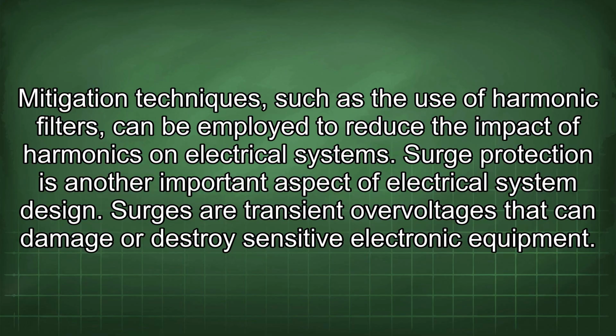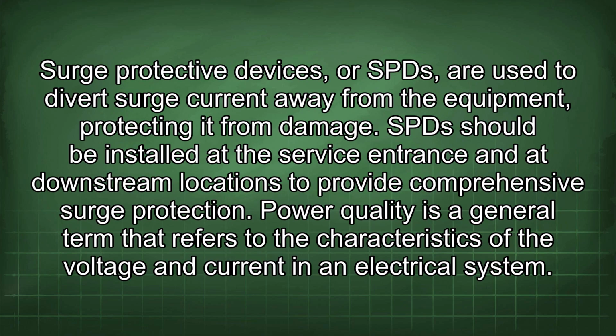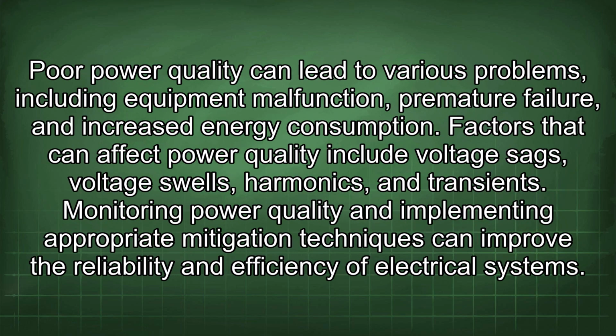Surge protection is another important aspect of electrical system design. Surges are transient overvoltages that can damage or destroy sensitive electronic equipment. Surge protective devices, or SPDs, are used to divert surge current away from the equipment, protecting it from damage. SPDs should be installed at the service entrance and at downstream locations to provide comprehensive surge protection. Power quality is a general term that refers to the characteristics of the voltage and current in an electrical system. Poor power quality can lead to various problems, including equipment malfunction, premature failure, and increased energy consumption.